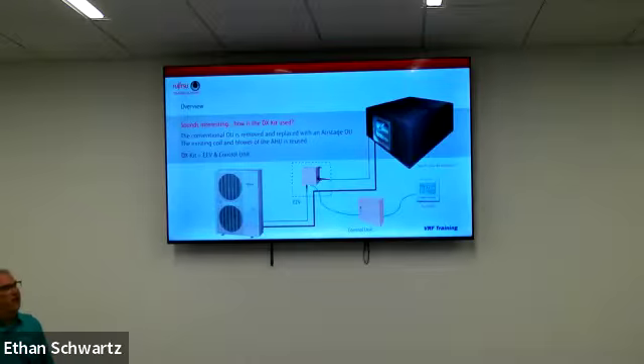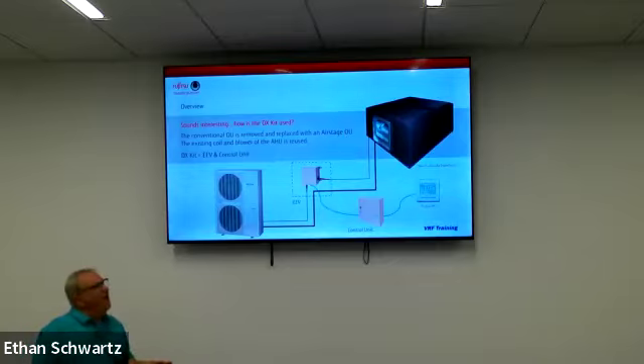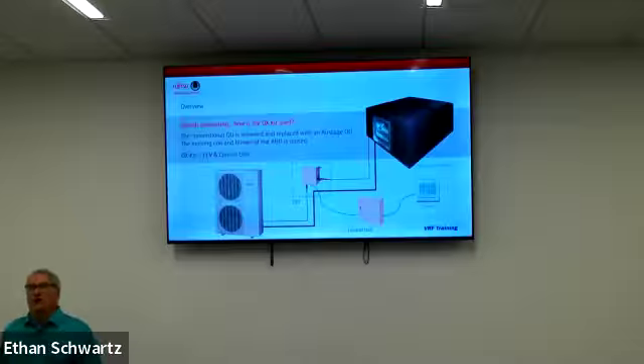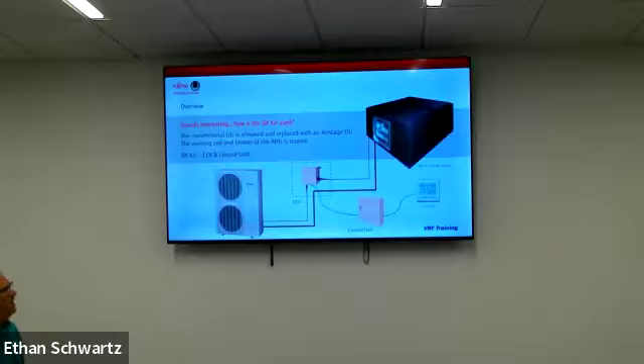We can then put air conditioning back into, or actually a heat pump back into, that air handler. I've done this, my largest is 80 tons, I think, with interlaced coils. Sometimes we can use the existing coils. Otherwise, we would have a new coil size. I do have coil sizing software on my computer, and we can make that selection.